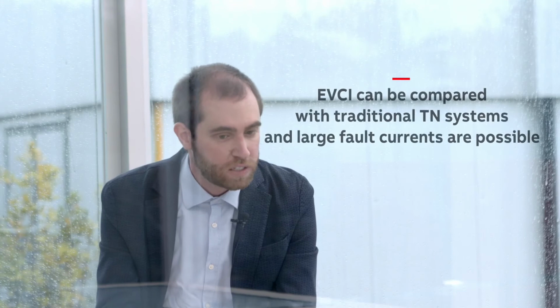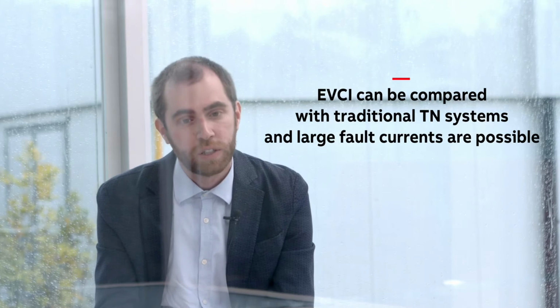We have three main points to consider in this system. Firstly, we can assess that this kind of system can be compared with a traditional TN AC power system, in which the ground fault currents can be pretty large, and for our hybrid AC-DC systems, we can say that our fault current can be closer in value to the one of the AC system, such that it is necessary to have circuit breakers with high breaking capacity and fast intervention time to avoid serious damage to the power converters.